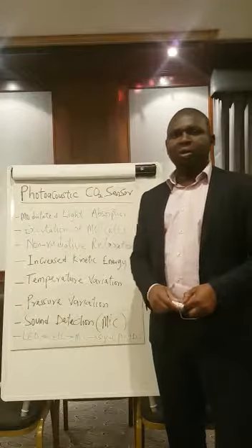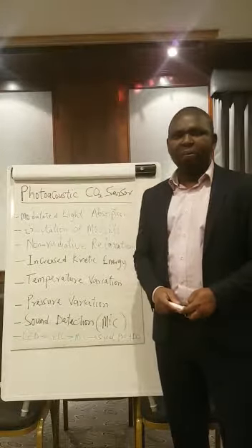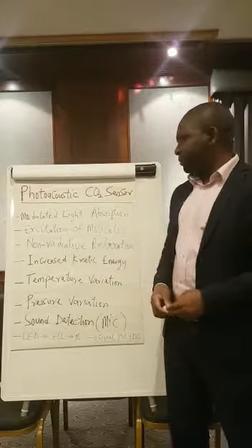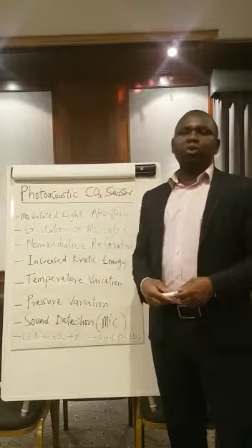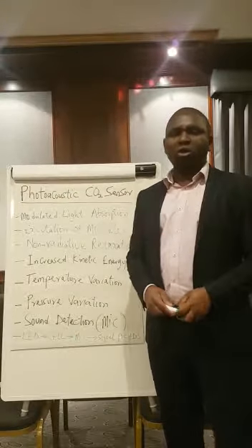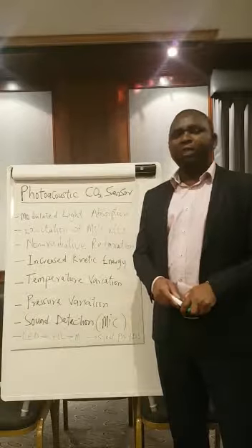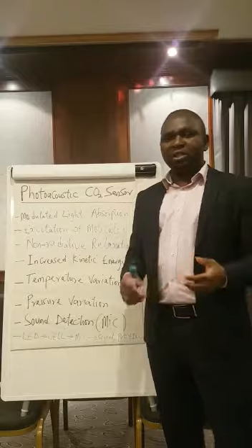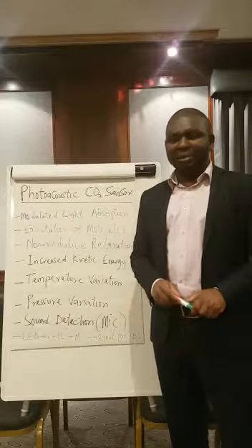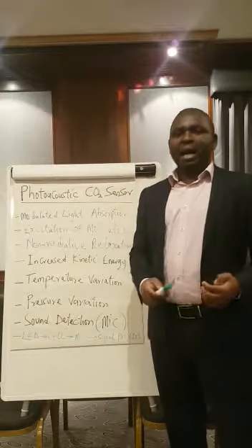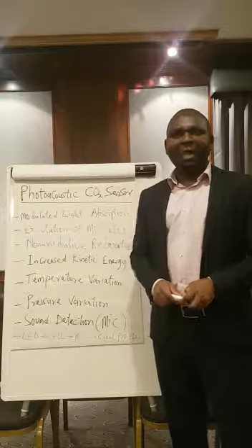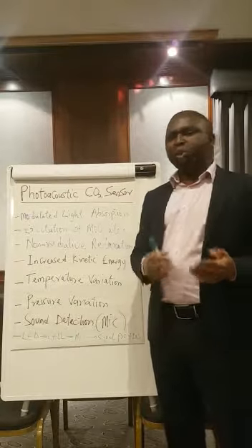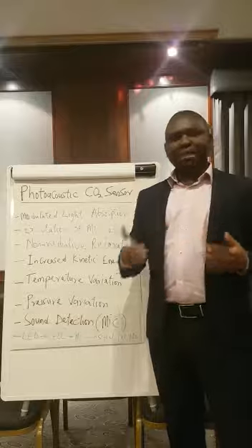I want to talk about a photoacoustic CO2 sensor that I designed. The photoacoustic CO2 sensor works on the principle of the photoacoustic effect. The photoacoustic effect was discovered in 1880 by Alexander Graham Bell. That photoacoustic effect actually works when modulated light passes through a sample.